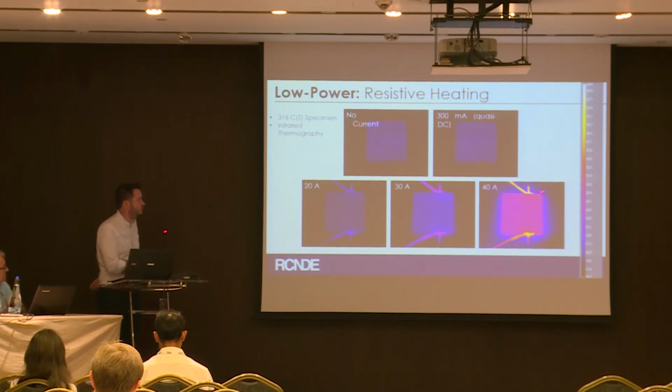Here, what you can see, I don't know if this is clear, is the CT specimen, and these are the cables we're using to introduce that current. And you can see that, of course, these are the first things that start to get hot, and in particular where you join that to the component. So in order to accommodate this 20, 30, or 40 amps, which you usually use for DC, you have to use very thick, impractical cables, which you sometimes have to join to a component.